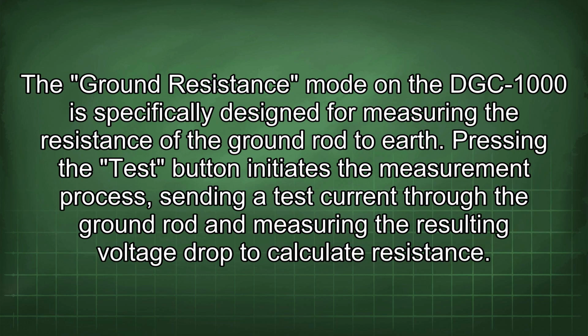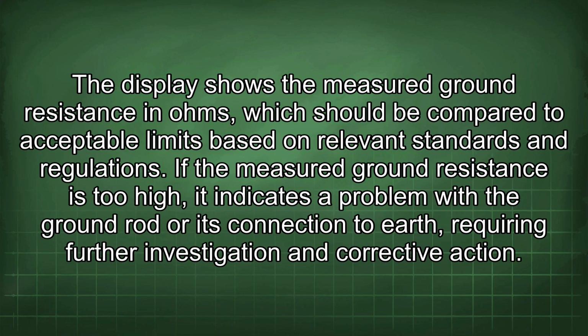The ground resistance mode on the DGC-1000 is specifically designed for measuring the resistance of the ground rod to earth. Pressing the test button initiates the measurement process, sending a test current through the ground rod and measuring the resulting voltage drop to calculate resistance. The display shows the measured ground resistance in ohms, which should be compared to acceptable limits based on relevant standards and regulations. If the measured ground resistance is too high, it indicates a problem with the ground rod or its connection to earth, requiring further investigation and corrective action.